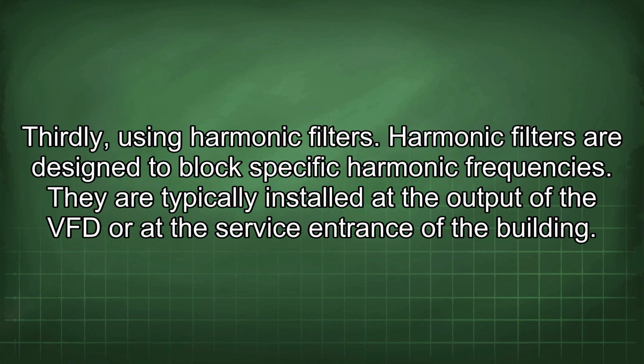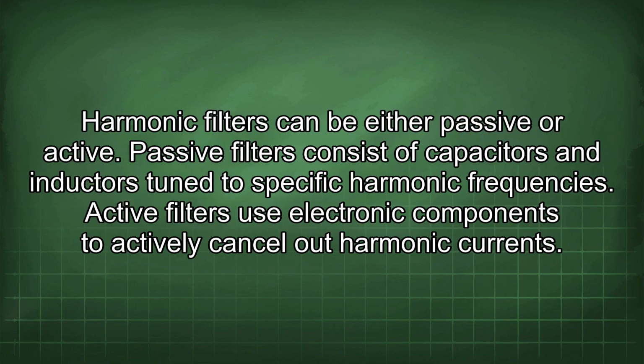Thirdly, using harmonic filters. Harmonic filters are designed to block specific harmonic frequencies. They are typically installed at the output of the VFD or at the service entrance of the building. Harmonic filters can be either passive or active. Passive filters consist of capacitors and inductors tuned to specific harmonic frequencies. Active filters use electronic components to actively cancel out harmonic currents.